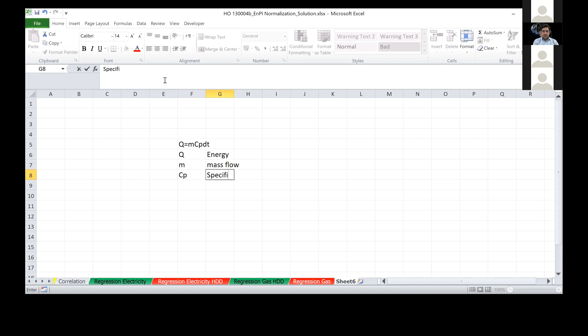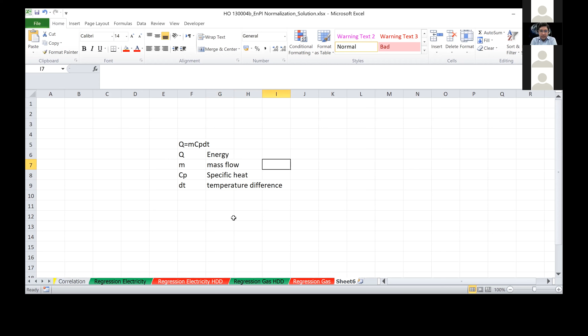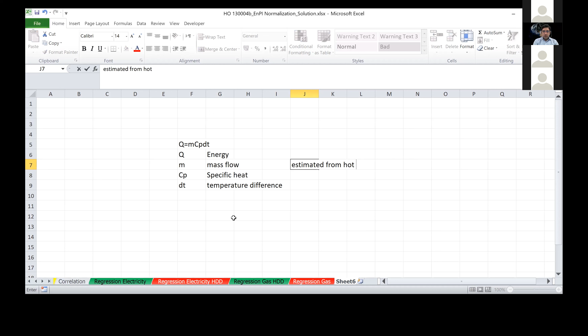So let's assume that we provide hot oil. Q is the amount of energy. We want to know how much energy is being consumed by a stanter. m is the mass flow rate of the thermal oil, and this we need to estimate, which we can try to estimate from the pumps that are pumping oil towards that stanter. So this needs to be estimated from hot oil pump data.